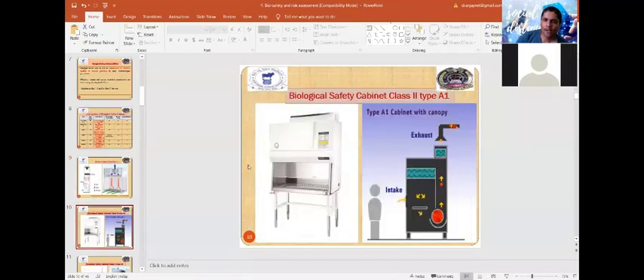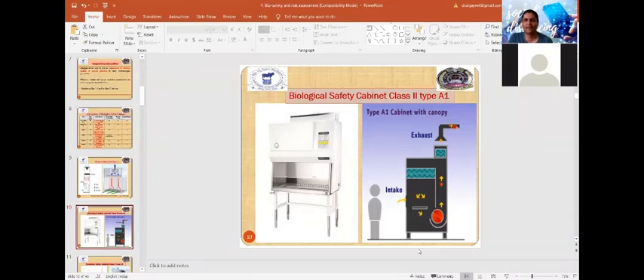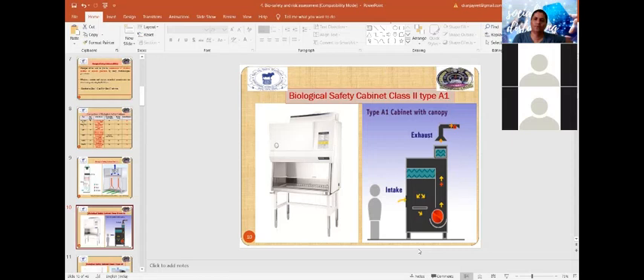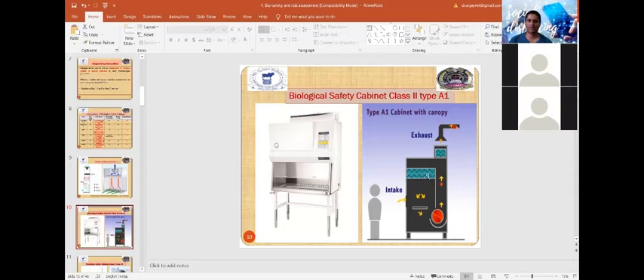An animated image is shown to illustrate the airflow patterns in the biosafety cabinets. For Type A1, the animation shows air inlets and outlets, and the recirculation mode through the HEPA filter, as well as exhaust through the HEPA filters. This helps understand how different cabinet classes manage air flow and recirculation.